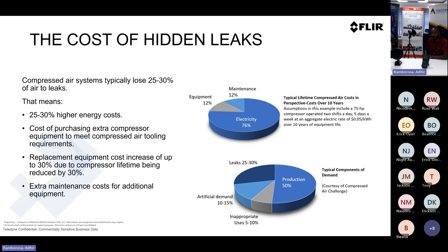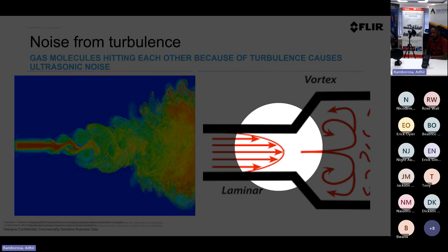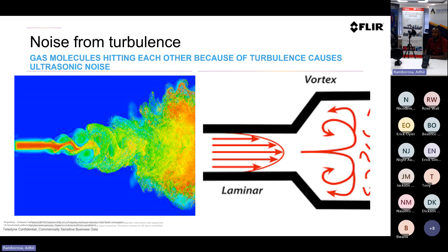Before we go too much into leaks, we need to understand a little bit about the science of it. If you look at the screen, you've got our laminar flow here, and a little breach or orifice coming out. You start to see that air leak creates turbulence, in the form of ultrasonic noise, beyond our normal hearing capability, so we wouldn't be able to hear it with our own ears. But using an instrument like this, we can pick it up, and based on that, we pick up this little vortex that comes out on the outside. That's how we visually start to look at it.